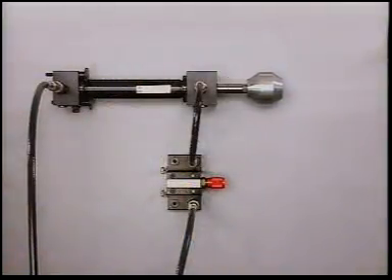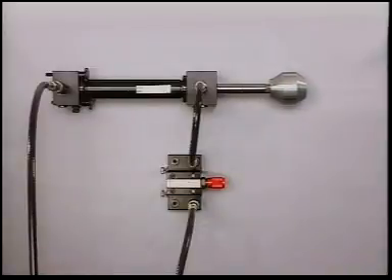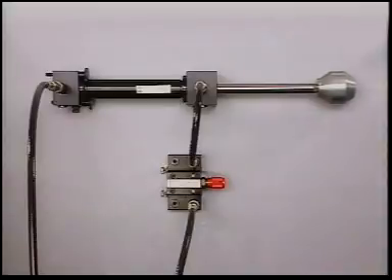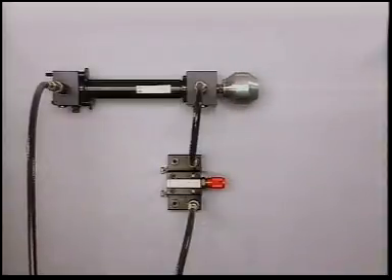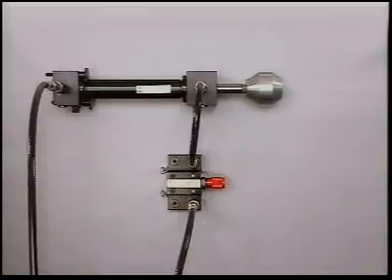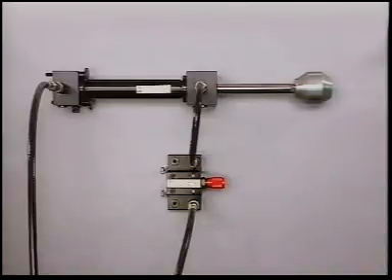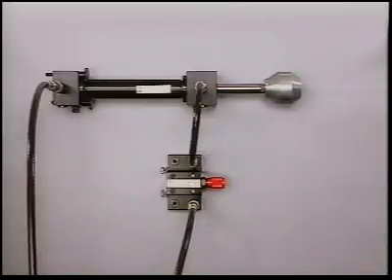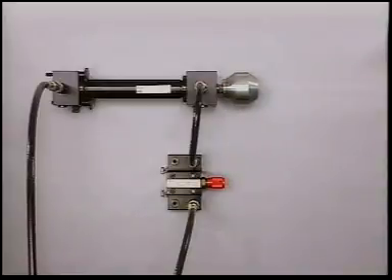So in a case like this, it's better to restrict the flow in the exhaust line. By this we mean that the flow of oil to the reservoir is restricted, because it doesn't matter if the oil heats up. At the same time, the cylinder piston is hydraulically clamped. But remember that the surface area ratio between the piston sides causes a transmission of pressure to take place. So the system must be suitable for the resulting high pressure.